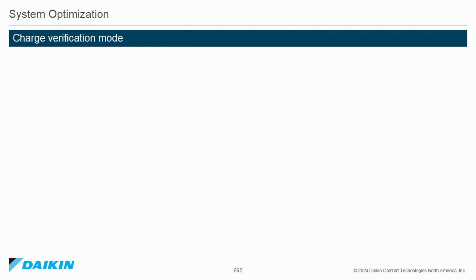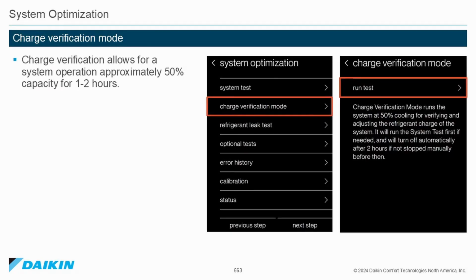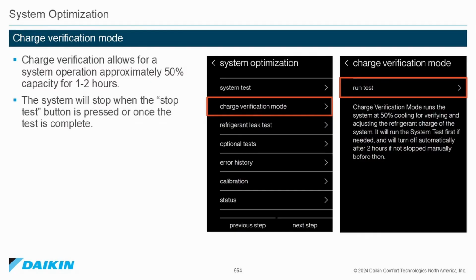Charge verification mode. Charge verification allows for a system operation approximately 50% capacity for 1 to 2 hours. The system will stop when the Stop Test button is pressed or once the test is complete. Note: for proper charging of the system, please see Equipment Installation Manual.